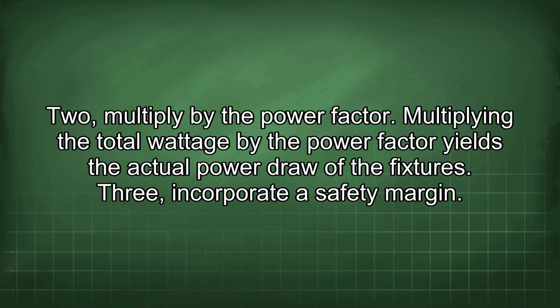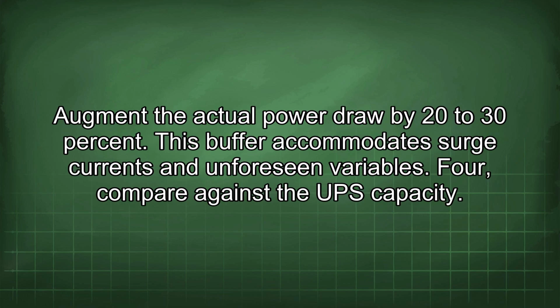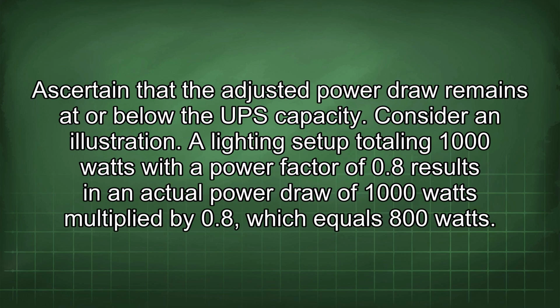3. Incorporate a safety margin. Augment the actual power draw by 20 to 30%. This buffer accommodates surge currents and unforeseen variables. 4. Compare against the UPS capacity. Ascertain that the adjusted power draw remains at or below the UPS capacity.